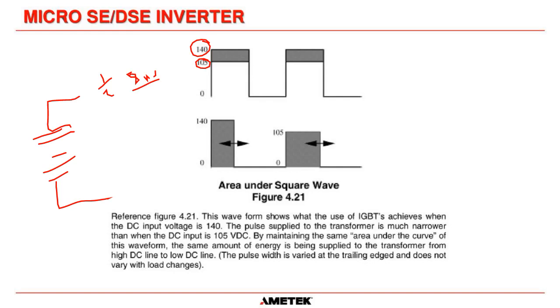So if the first area here is at 140 volts, let's say we only need to switch the IGBT on for half of that cycle, so that would be 4 milliseconds. If you do the math, 4 times 140, the area under that square wave is 560.